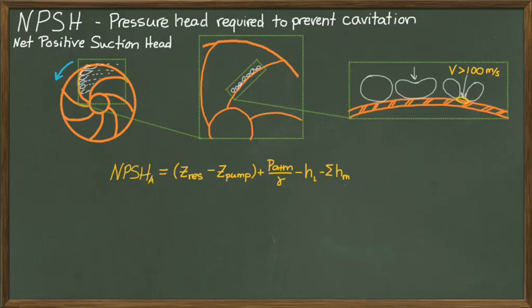We must also account for all friction and minor losses between the reservoir and the pump suction. Finally, we must also account for the vapor pressure head of the fluid itself, which is a function of the temperature of the fluid.